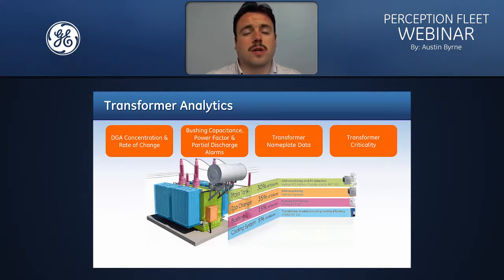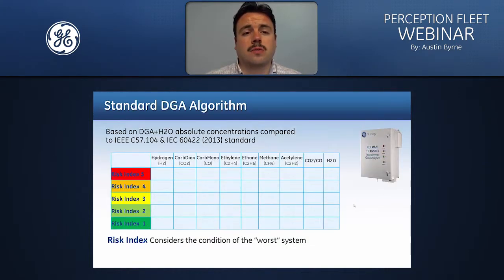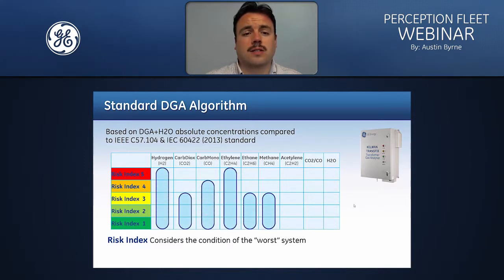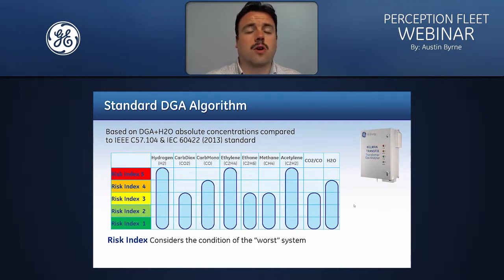The first algorithm we're going to look at is the standard DGA algorithm, which is based on DGA and moisture absolute concentration analysis. The rules that are built in the algorithm are taken directly from the IEEE C57.104 and IEC 60422 standards. You can see the different gases in the table and how their risk indexes may be applied. So for example, hydrogen can reach a risk index of 5 because it's seen as being a critical fault gas, whereas carbon dioxide is considered not to be a serious indicator of a fault, so it can only reach a risk index of 3.